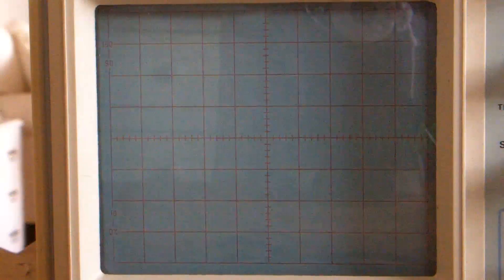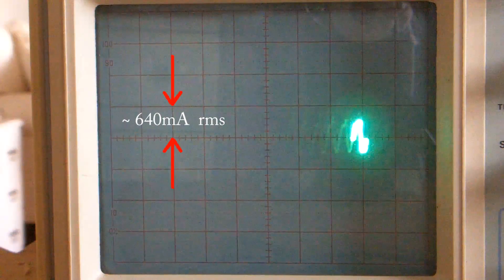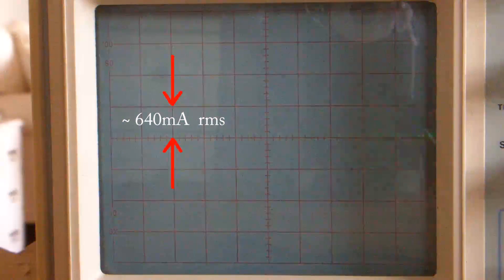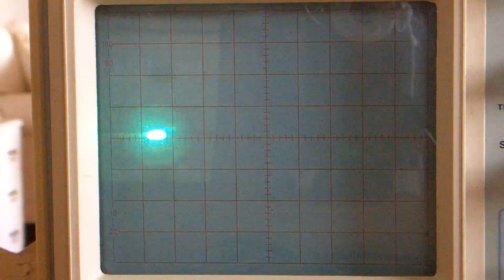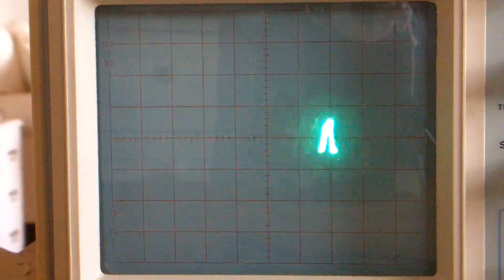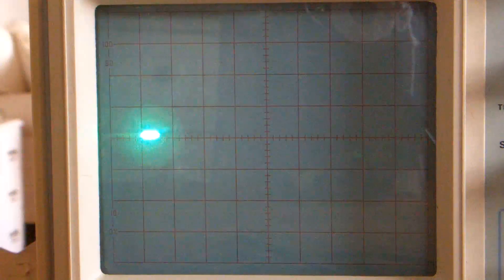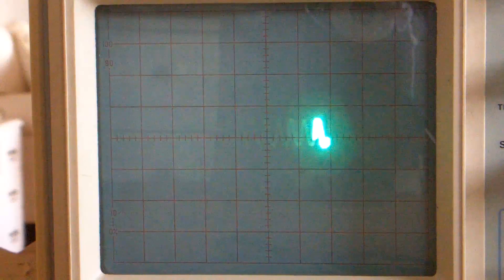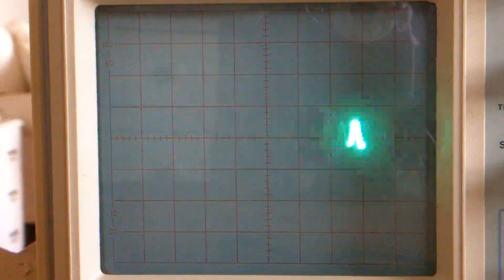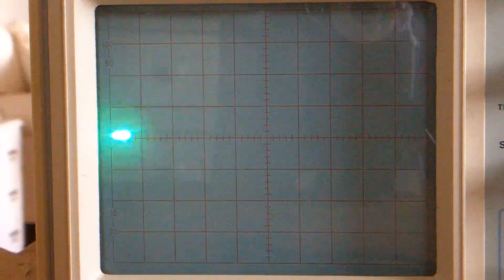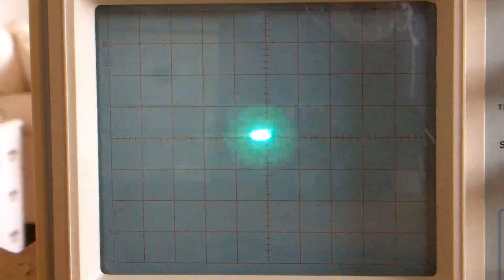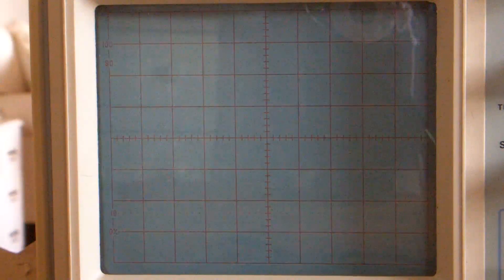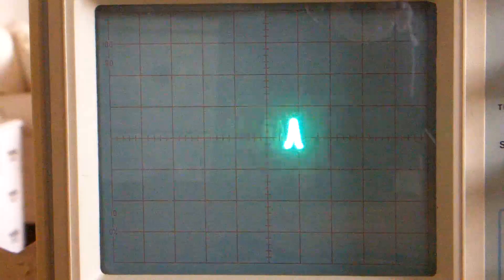What you'll see is a random nature to the way that the magnetizing current is drawn. That has to do with the moment in time in the mains cycle when we actually switch the transformer on, and it also has to do with the remnant state of the magnetism.